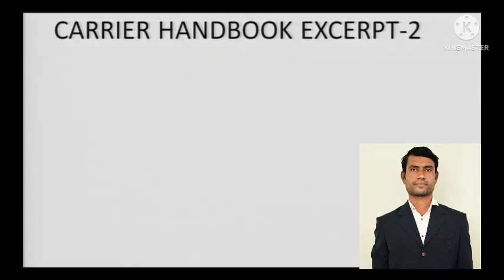The Carrier Handbook uses IP — imperial units — with degrees Fahrenheit and BTU per hour per square foot. Looking at the masonry units section, for brick common, 4 inches of thickness gives a resistance of 0.8. So for 8 inches you multiply by 2, for 16 inches multiply accordingly — just apply the appropriate multiplier to get the resistance for your specific brick wall thickness.